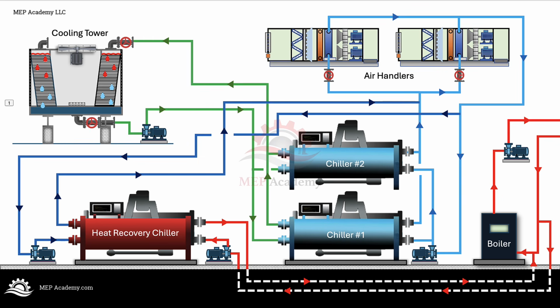But there is one important rule. A heat recovery chiller works best when there is a cooling load and a heating load at the same time. If the building needs chilled water but has no useful place to send the recovered heat, then the heat still has to be rejected somewhere. That may be a cooling tower, fluid cooler, dry cooler, or another heat rejection device. And if the building needs heating but does not have enough cooling load available, then the heat recovery chiller may not have enough heat to recover.